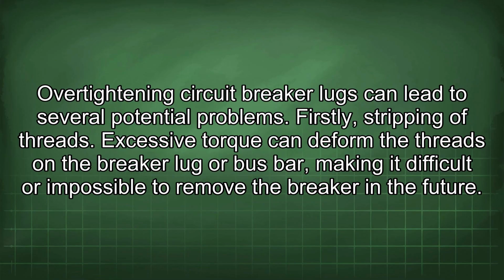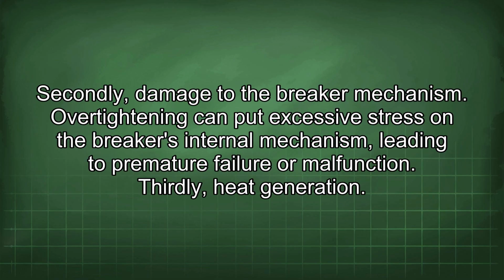Over-tightening circuit breaker lugs can lead to several potential problems. Firstly, stripping of threads. Excessive torque can deform the threads on the breaker lug or bus bar, making it difficult or impossible to remove the breaker in the future. Secondly, damage to the breaker mechanism. Over-tightening can put excessive stress on the breaker's internal mechanism, leading to premature failure or malfunction.